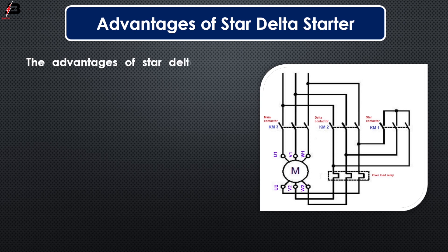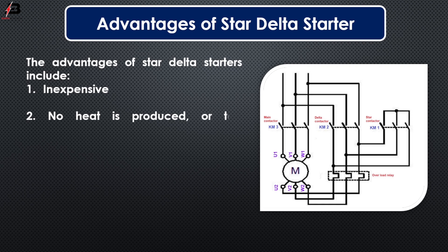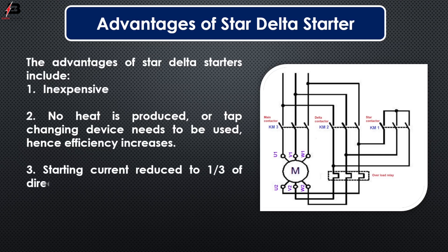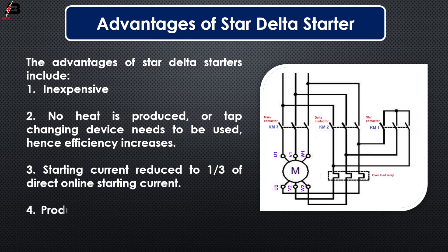Advantages of star delta starter: The advantages include: 1. Inexpensive. 2. No heat is produced and no tap changing device needs to be used, hence efficiency increases. 3. Starting current is reduced to 1/3 of direct online starting current. 4. Produces high torque per ampere of line current.